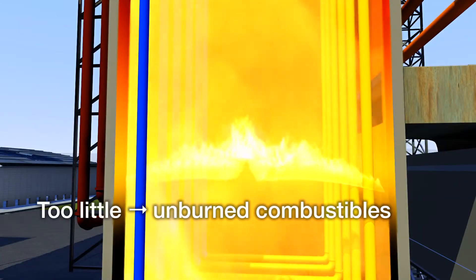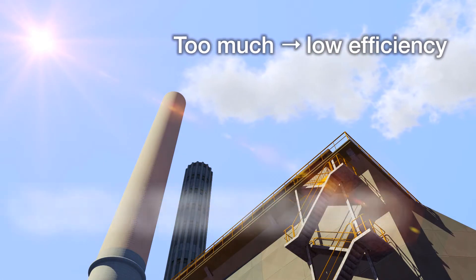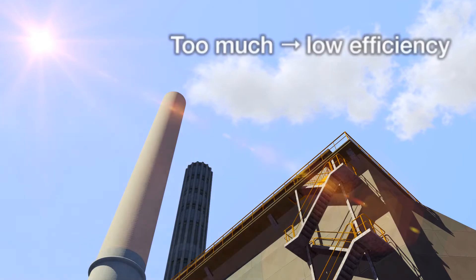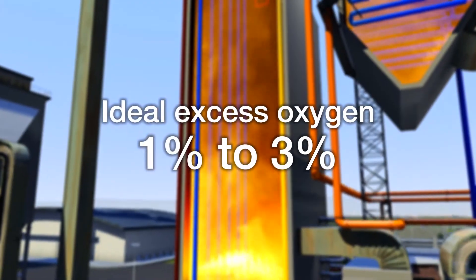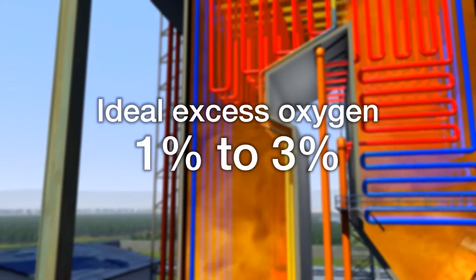Whilst too little air will produce unburned combustibles, too much air will reduce combustion efficiency, with heat being lost via the stack as hot flue gases. An ideal figure for excess oxygen is between 1 and 3%, depending on a range of factors, including the fuel being combusted, the steam load, and the condition of the boiler burner.